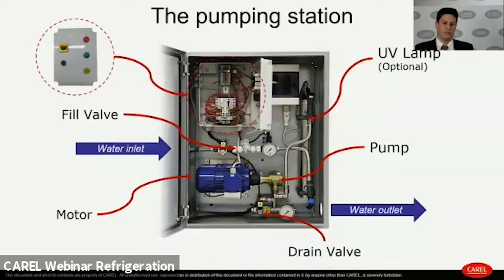The pumping station is divided into two main parts. We have an electrical panel on the top left of the picture and a hydraulic part. The aim of the pumping station is to take water from the grid and increase the pressure in order to nebulize water through nozzles. The main component, of course, is a pump. The pump is available in quite a wide range. So we have 3 sizes available, starting from 100 liters per hour, 500 liters per hour, and 1000 liters per hour. This allows the solution, chillBooster, to be flexible in terms of water output. So we can fit the request by varying the size of the pumping station.